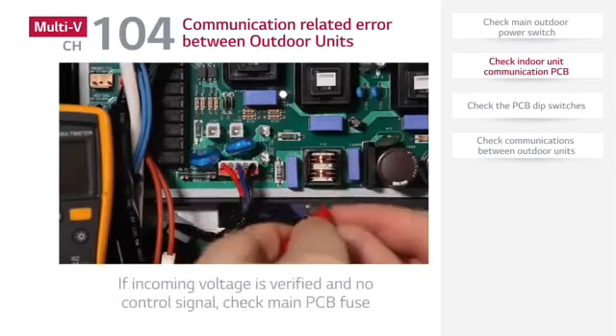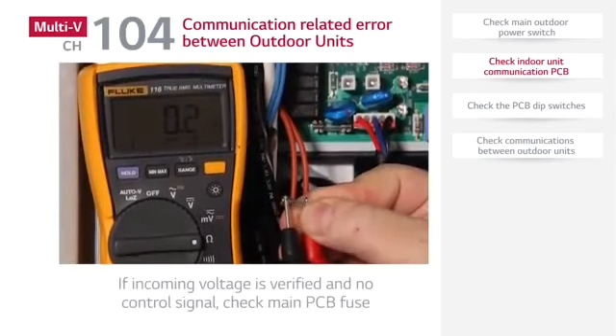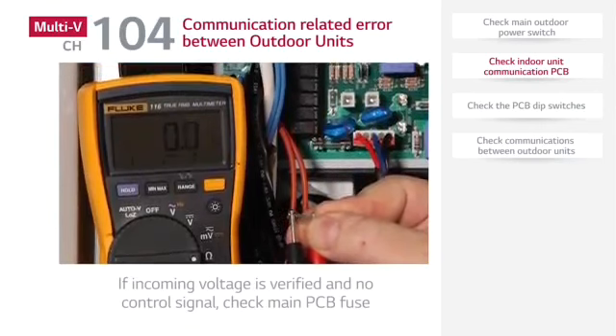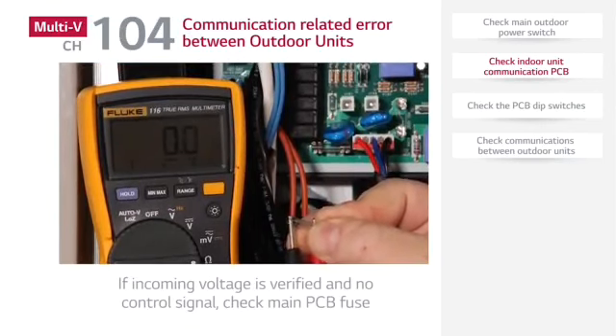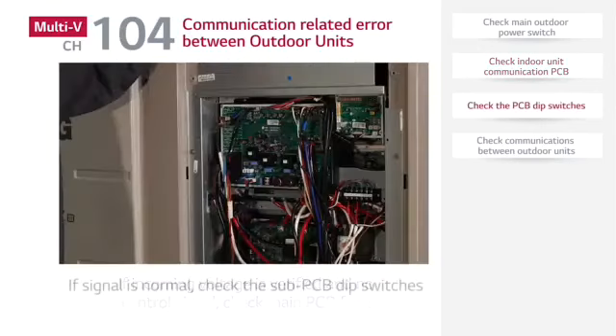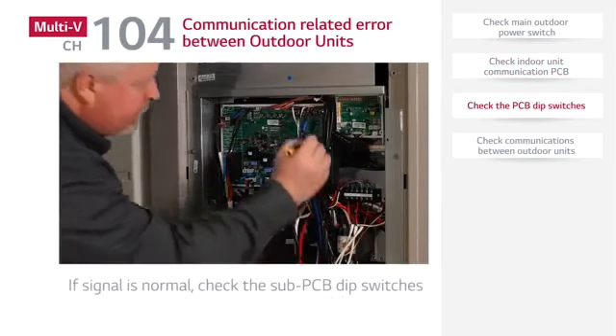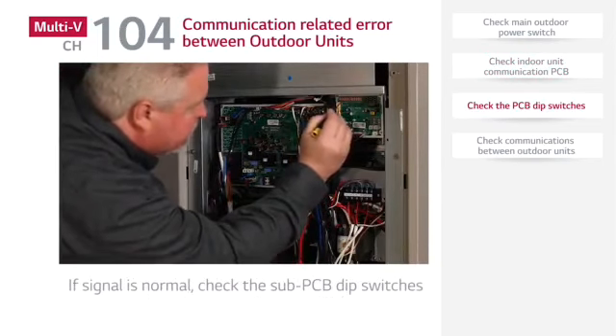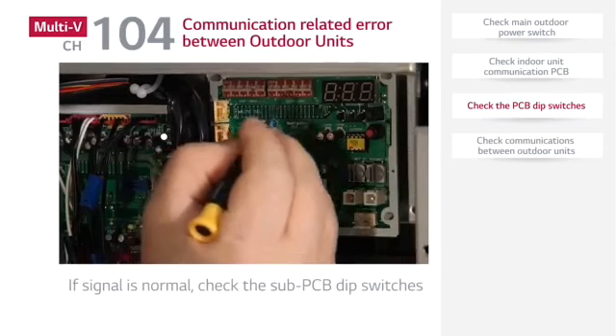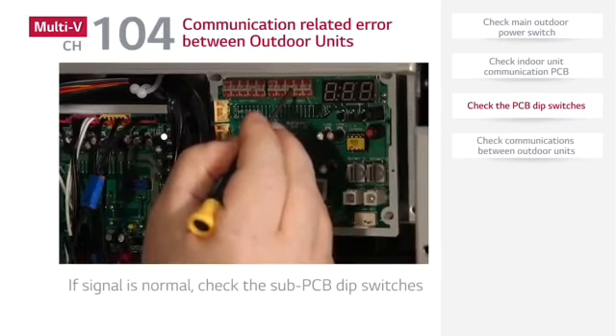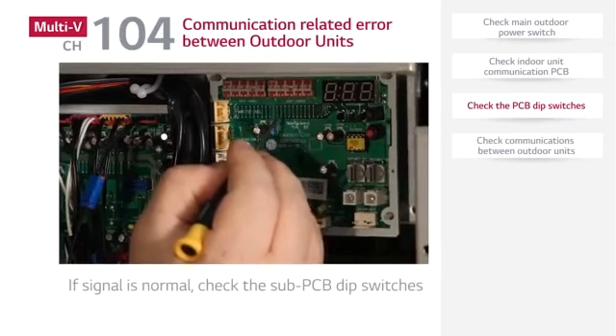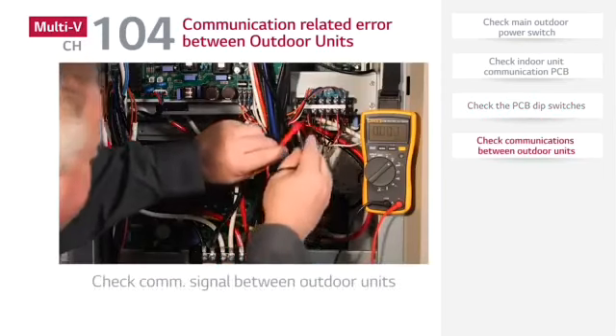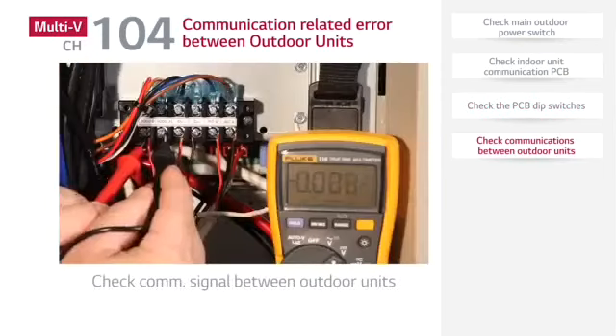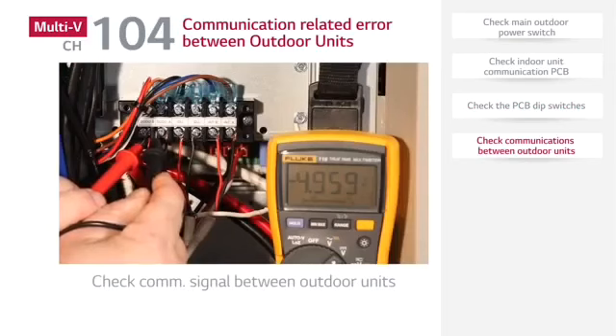If the incoming voltage is verified and there is no control signal, check the main PCB fuse. If the fuse tests good, replace the main PCB. If the signal is normal, check the sub-PCB dip switches. If there is no problem with the dip switch settings, check the communication signal between outdoor units.